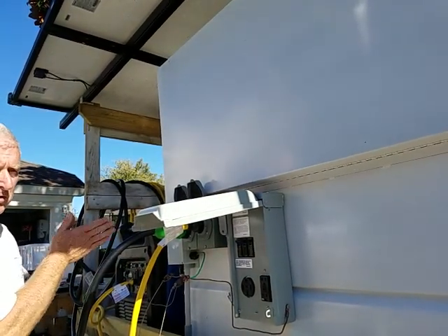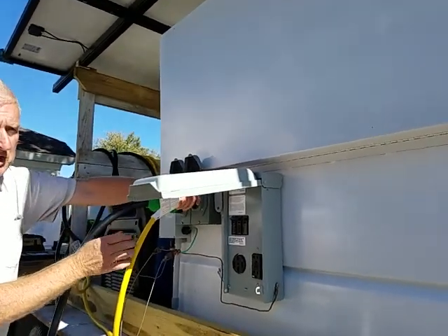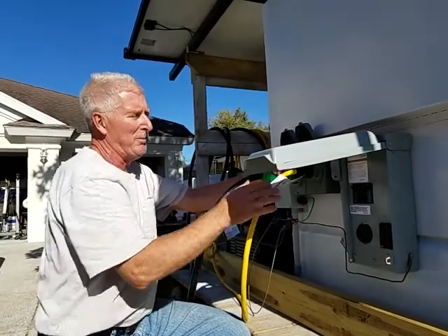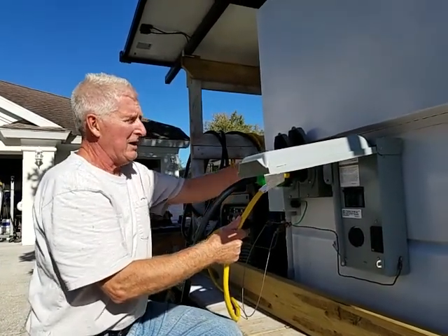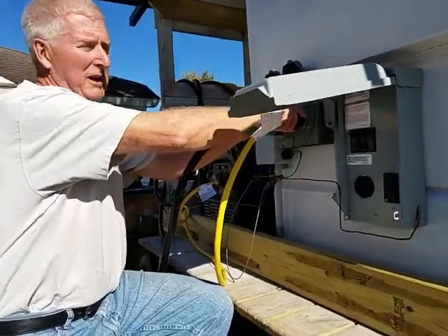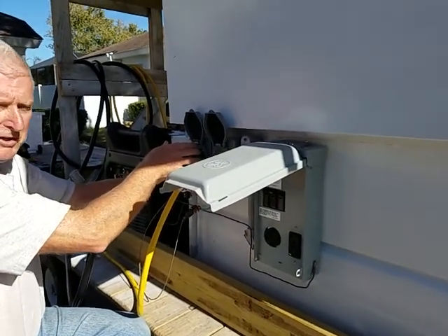The inverter output goes to the same AC bus as the grid input and as the generator input. These two can't be connected at the same time because you can't have the grid backfeed the generator. But any two of these can be paralleled. So the inverter output can be paralleled with the generator. The inverter output can be paralleled with the grid.